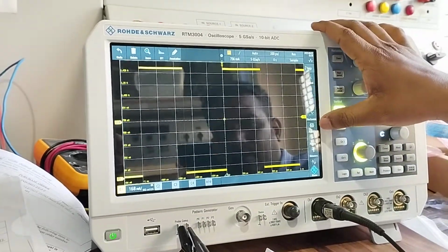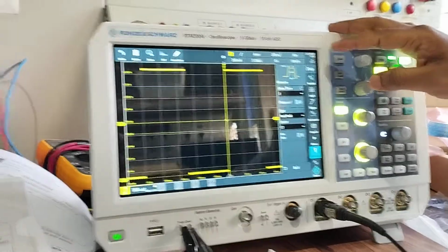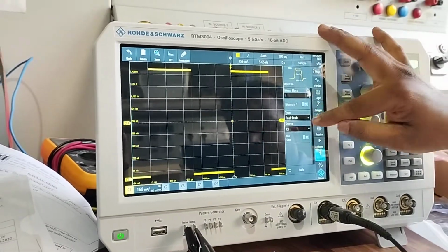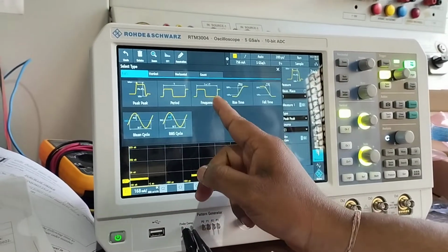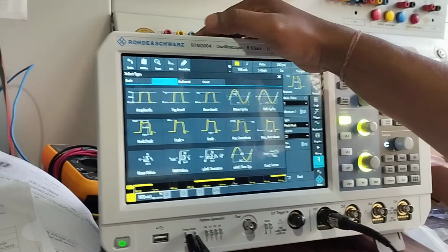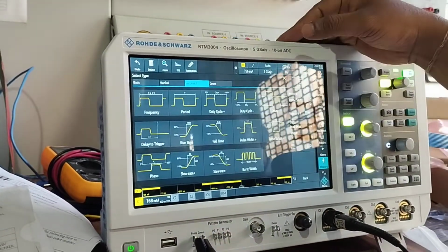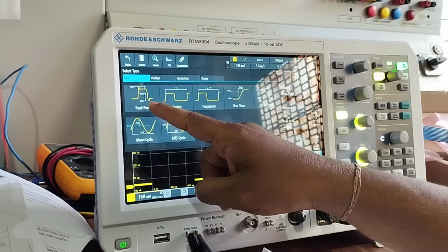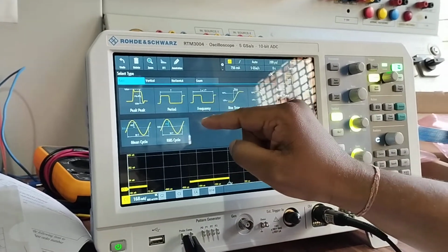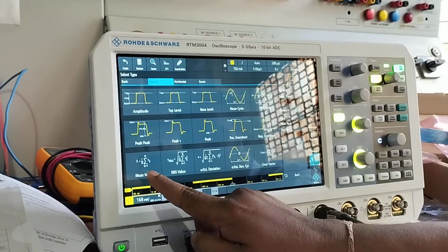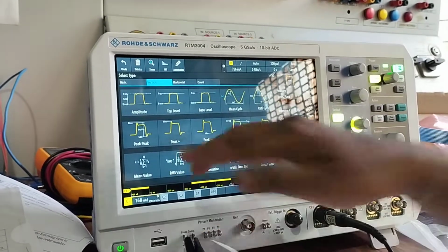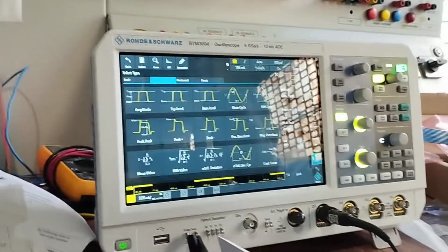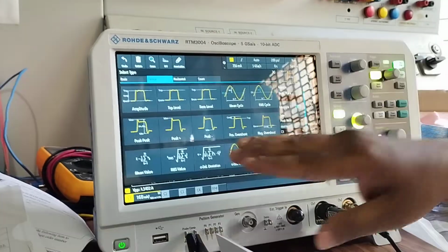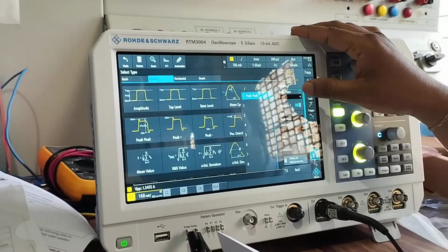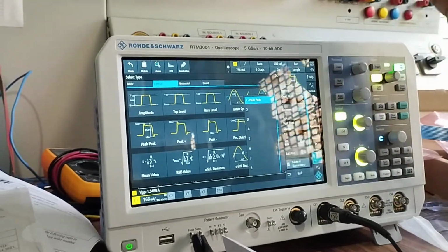Okay, after the acquisition algorithms, there are also our measurements. In measurements, in the basic group we have around 7 measurements, and in the vertical we have this many, and in the horizontal we have the count. If you look at anything, you can see from where to where it is measuring peak to peak, and from where to where it is measuring period. And in the vertical, if you look at the mean value and RMS value, they are giving the formula on what basis they are doing the measurements. In total there are 34 measurements, but on the display it will show only 8 measurements at a time. You can select any 8 of those.